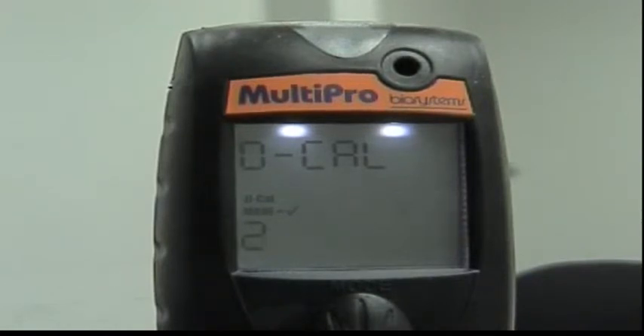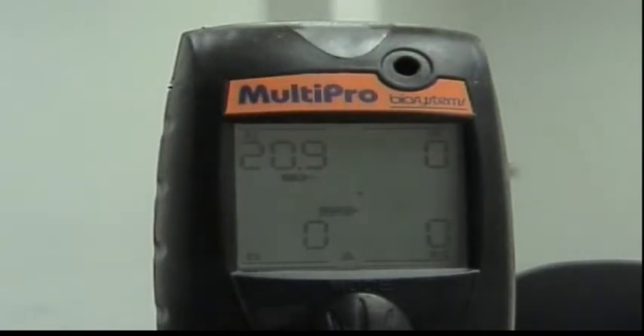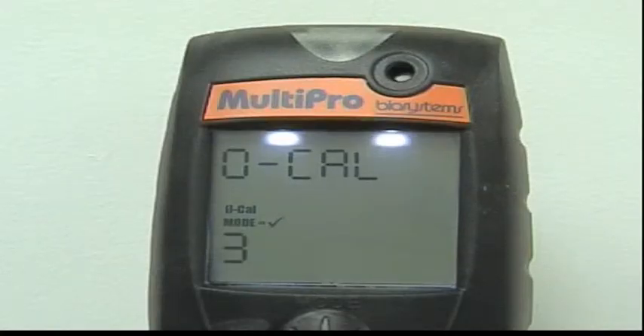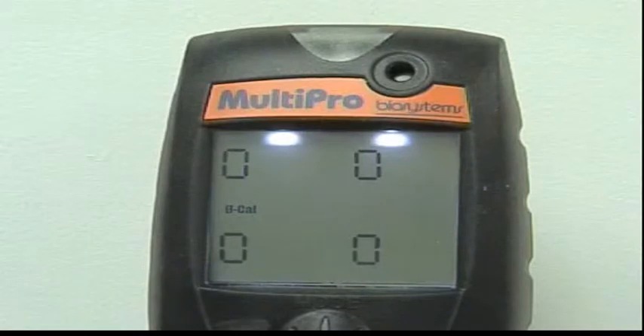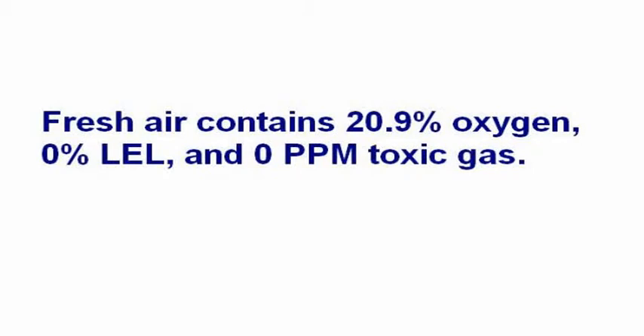To return to the current gas reading screen and bypass the fresh air 0 calibration, allow the clock to count down without pressing the mode button. To initiate the fresh air calibration sequence, press the mode button before the unit completely counts down to 0. The instrument will automatically adjust the oxygen, combustible gas, and toxic gas readings to match the concentrations expected in a fresh air environment: 20.9% for oxygen, 0% LEL for combustible gas, and 0 parts per million for the toxic gases.